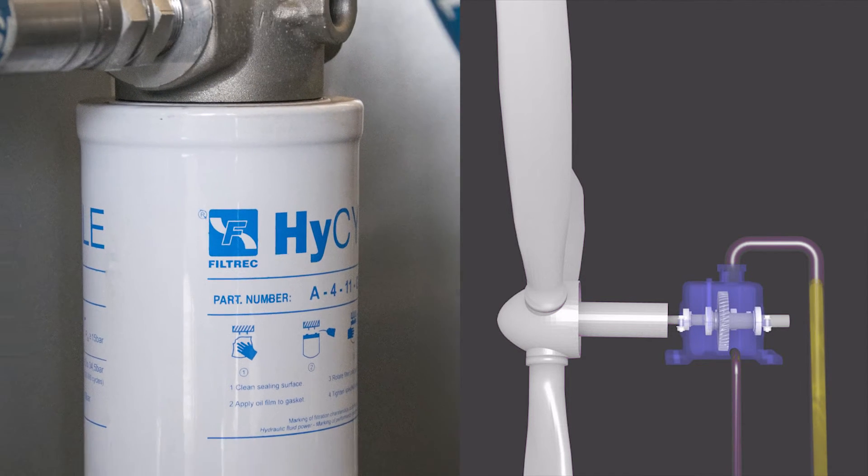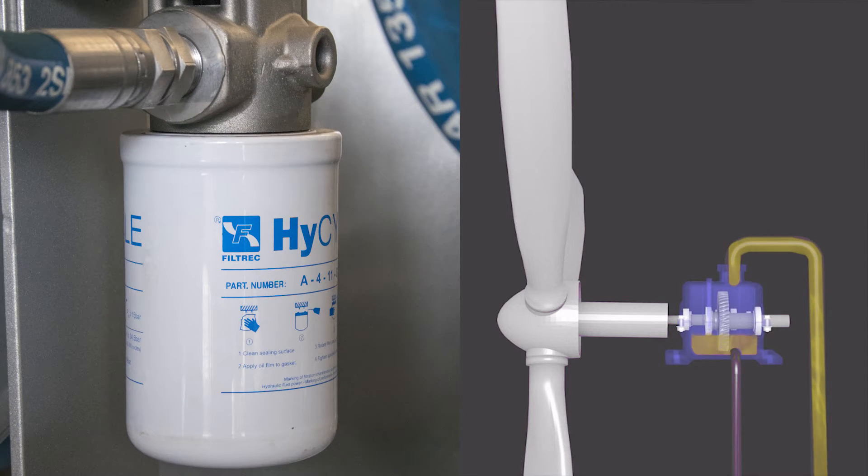Filtration mode: During the filling of new oil or flushing oil into the wind turbine gearbox, the oil in the system passes through a filter of 15 micron for additional purification from mechanical impurities.